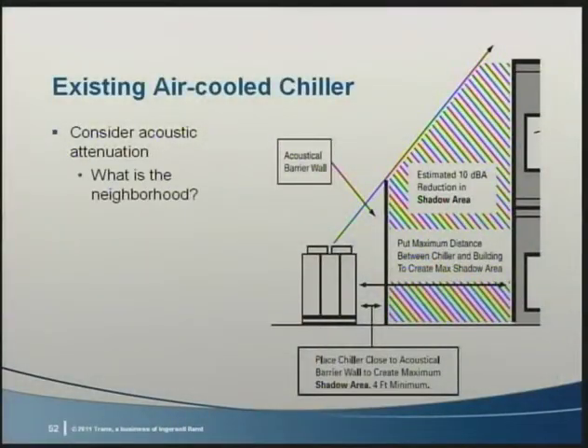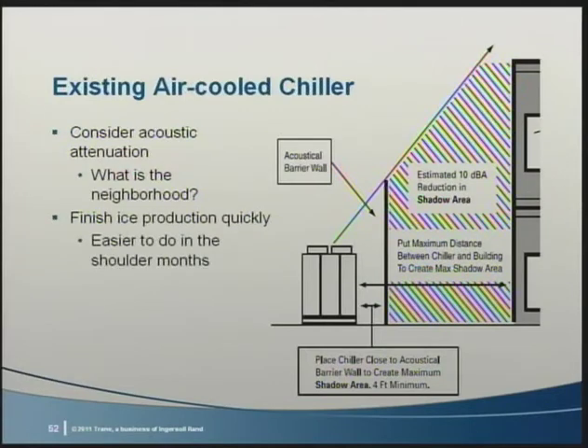Depending on the hours when tanks will be charged, you may want to consider some acoustic attenuation modifications. Consider the neighborhood. Chillers making ice tend to be louder than they normally would have been, and this change in acoustic signature is a lot more obvious when it's quiet at night and in the early morning. Is this application in a residential neighborhood? Is it on a lower roof with taller buildings adjacent? Many times of the year, ice production can be completed in the early evening hours, or the ice charge can last more than one day.